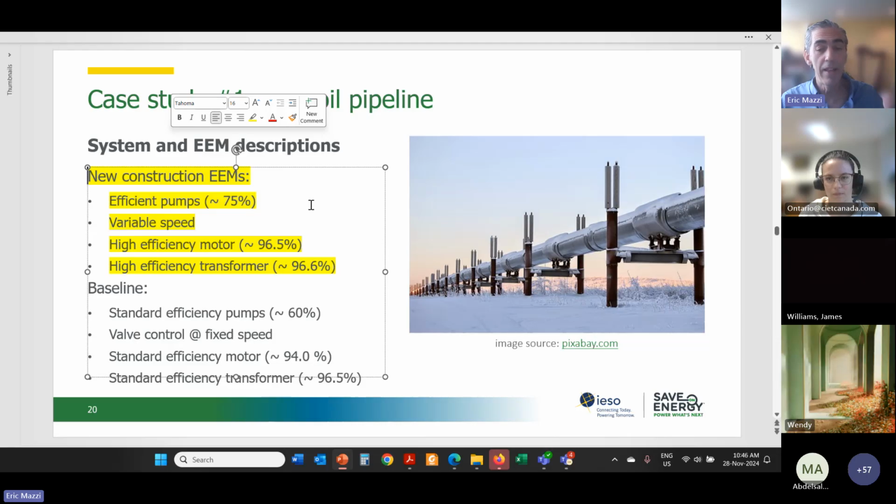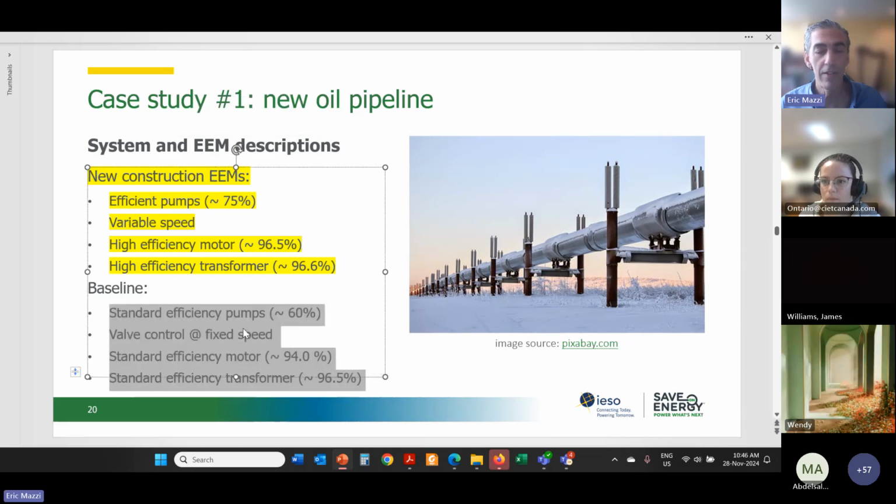And so that builds that modeling and process expertise. And you want to calibrate that model to some agreed upon number, which I tend to use 5%, but you could use a different number depending on your project circumstances. Then the next step is, okay, what would have been the electricity consumption if the plant expansion had been with these efficiencies that I'm highlighting here in green.